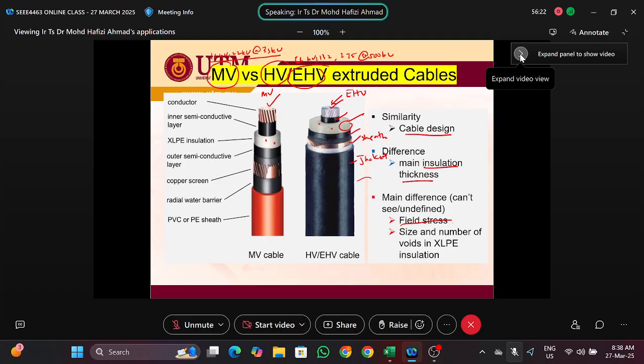Okay, why? Because of the higher voltage, something like 275 kV or 500 kV, the electric field is more than the medium voltage cable. So that's why it cannot accept more gas filled voids or air filled voids inside the XLPE. Okay, so that's why these cables, either medium voltage cable or extra high voltage cables, must be tested. There must be commissioning before they are allowed to be applied or to be installed in the field. Okay, all right.